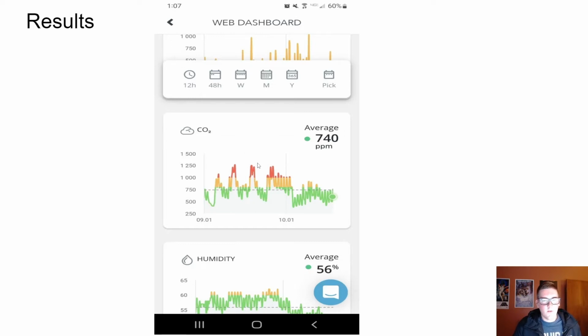So you can see this was pre-ERV installation here, and on about 10.1 when I did install it, the CO2 average drastically improved if you were to take the average of this time versus this time. And you can also tell that when we would leave to go out, the CO2 took a long time to dilute and go down. It would take hours because the house is sealed pretty well. Whereas when you've got an ERV, that CO2 is almost dropping instantly. And you can see every time it's kicking on, you get those reductions. So that was pretty cool to see the results.